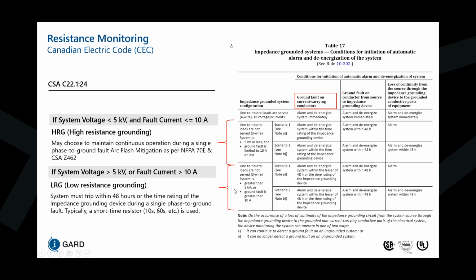When it comes to low resistance grounding, depicted as the third row in this table, low resistance grounding is more important for reducing the energy available for a phase to ground fault to a specific value. So rather than having kiloamps of ground fault current, we're limiting to a value somewhere between 25 to 400 amps, and then allowing our ground fault pickup schemes downstream to be more sensitive to ground faults, and thereby creating a bit of a safer environment. Even though these are at hundreds of amps, it's better than having thousands of amps, I would say.